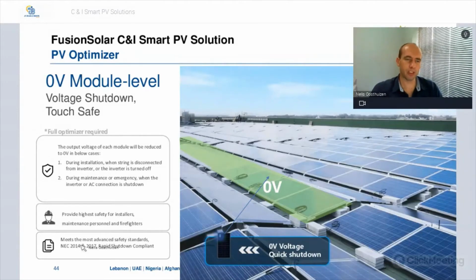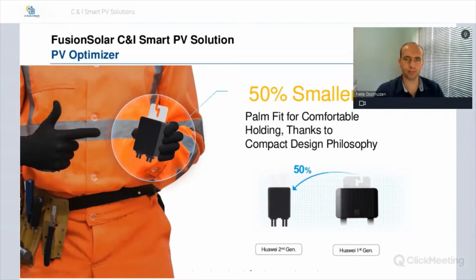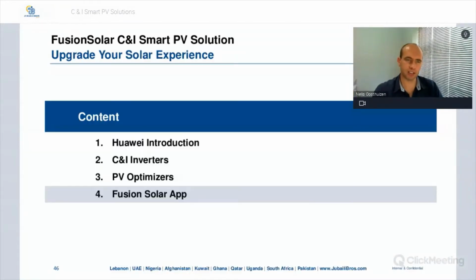And then the Huawei optimizers meet the most advanced safety standards, NEC 2014 and 2017, and are compliant with rapid shutdown. This is just a slide showing how the Huawei optimizers have improved from the first generation to the second generation. They've become 50% smaller, which allows them to fit in the palm of your hand. It's comfortable, and the design philosophy is a lot more compact.